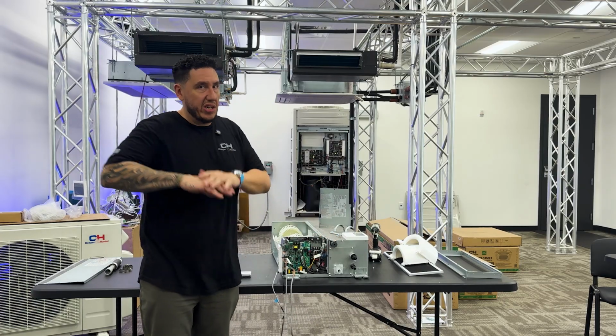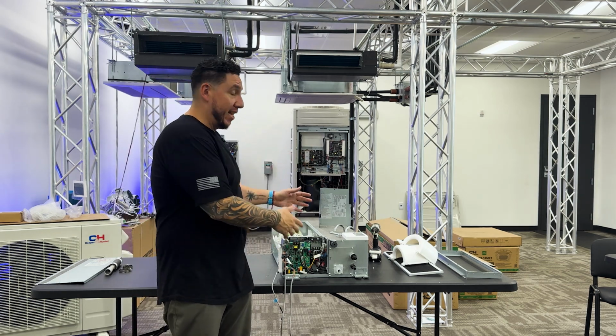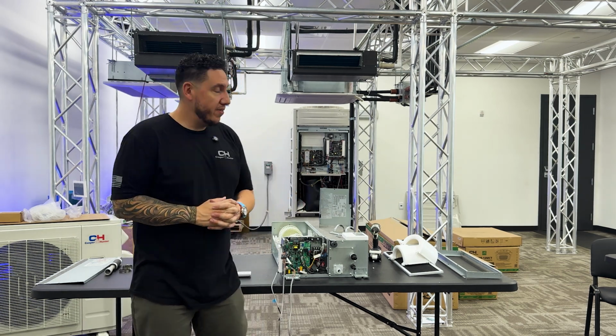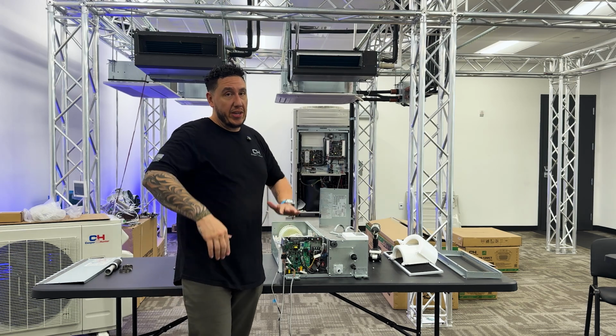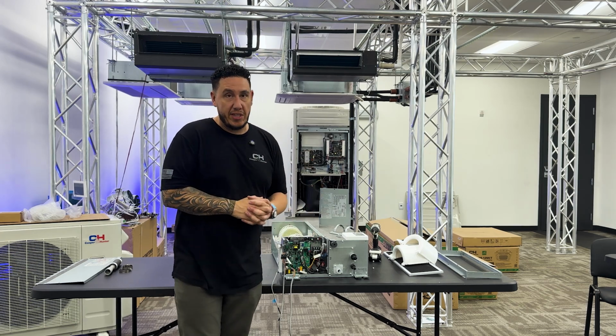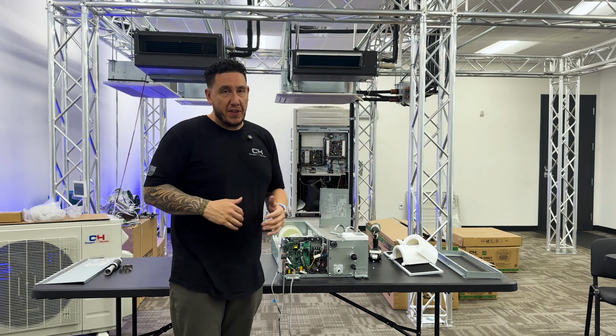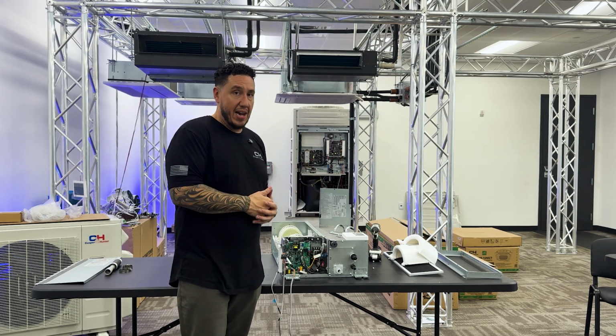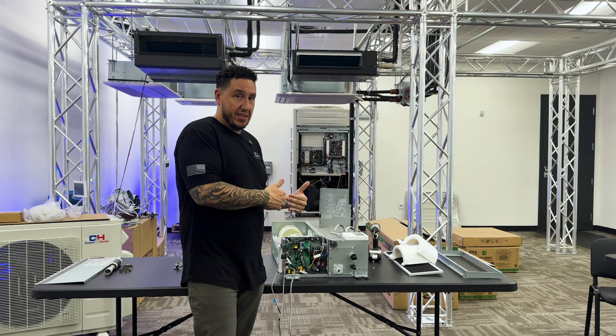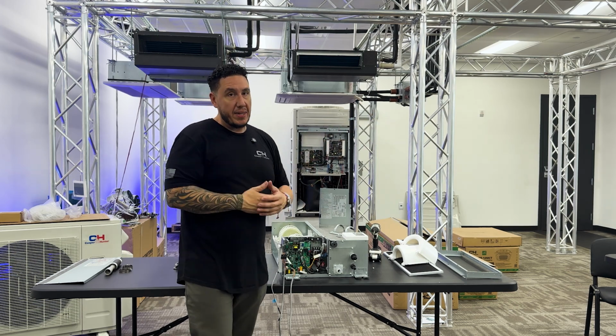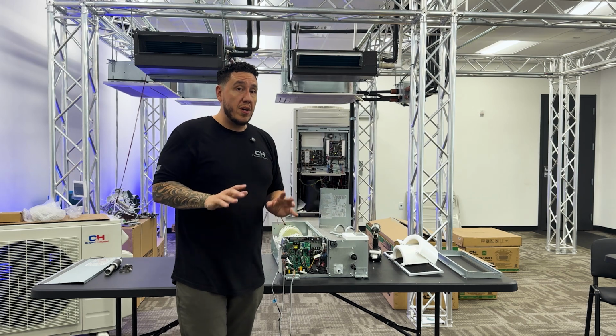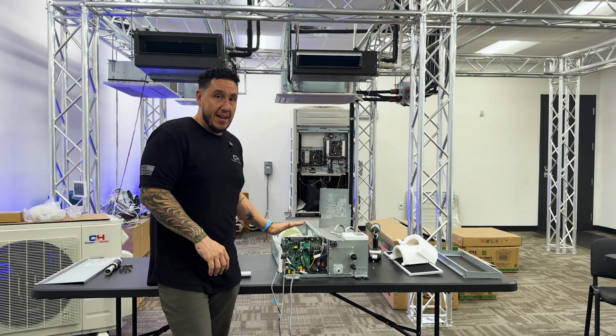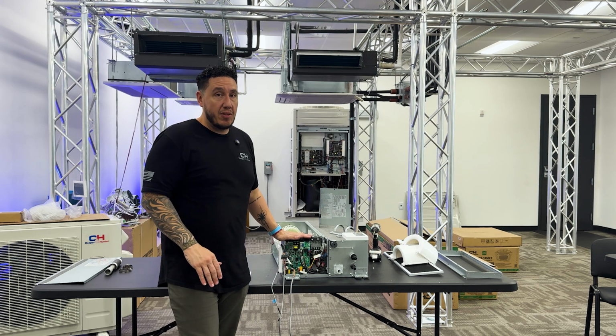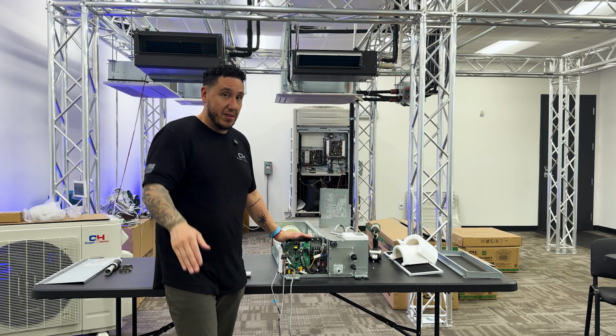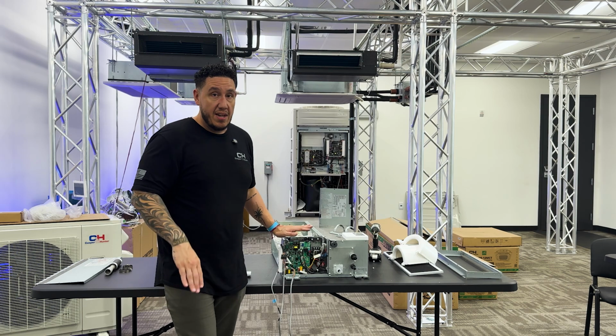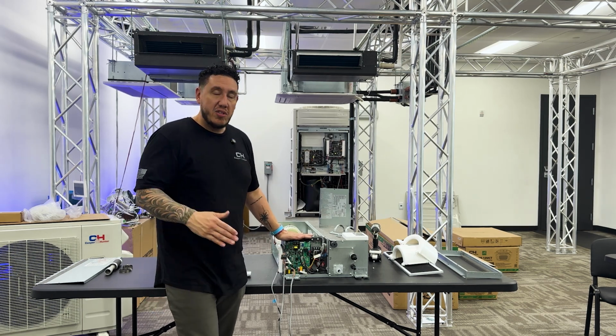So this unit here, just like all the other Cooper&Hunter equipment, can be installed as a single zone one-to-one application. Again, remember, I have dip switch settings, so I could go between 6, 9, or 12,000 BTU. On a multi-zone, that is a great feature to have if they need to make any changes on the fly. If they've oversized the unit, they could adjust the size of it, or if they undersize, they could increase the BTU. But if it is a single zone, one-to-one install, they have to match that dip switch setting to the BTU capacity of the outdoor compressor. So if it's a 9,000 compressor, this has to be set to 9,000. If it's a 12,000, it has to be set to 12, so on and so forth.